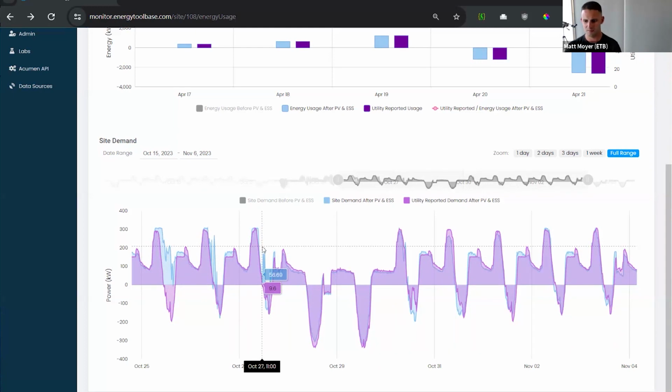So what happened ultimately for the cost? Did they get a credit back from the utility? They did. This one in particular ended up being a $17,000 refund from the utility, and we were able to use this data here, along with the bill calculations we have in Monitor, to go through the full refund process, and got a $17,000 credit for the customer.